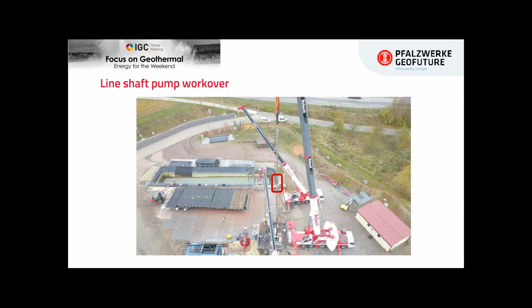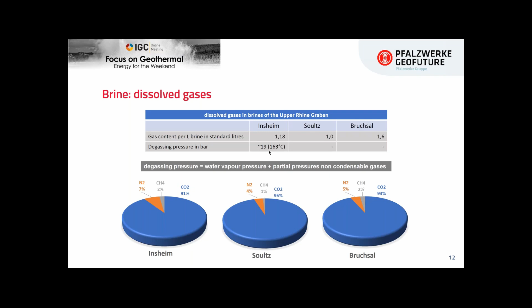By operating a brine circuit, we always have to keep in mind the chemical issues and conditions of our brines, shown here with the basic data, especially the carbon dioxide content, which is very high in the Upper Rhine Graben, ranging from 91 to even 95% carbon dioxide in the gas phase. Usually we have an average value of 50% volume in our brine, so 50% is water and 50% is gas. Therefore the brine system is operated on the hot side with an operating pressure above 20 bars, so we can avoid degassing effects in the brine circuit.